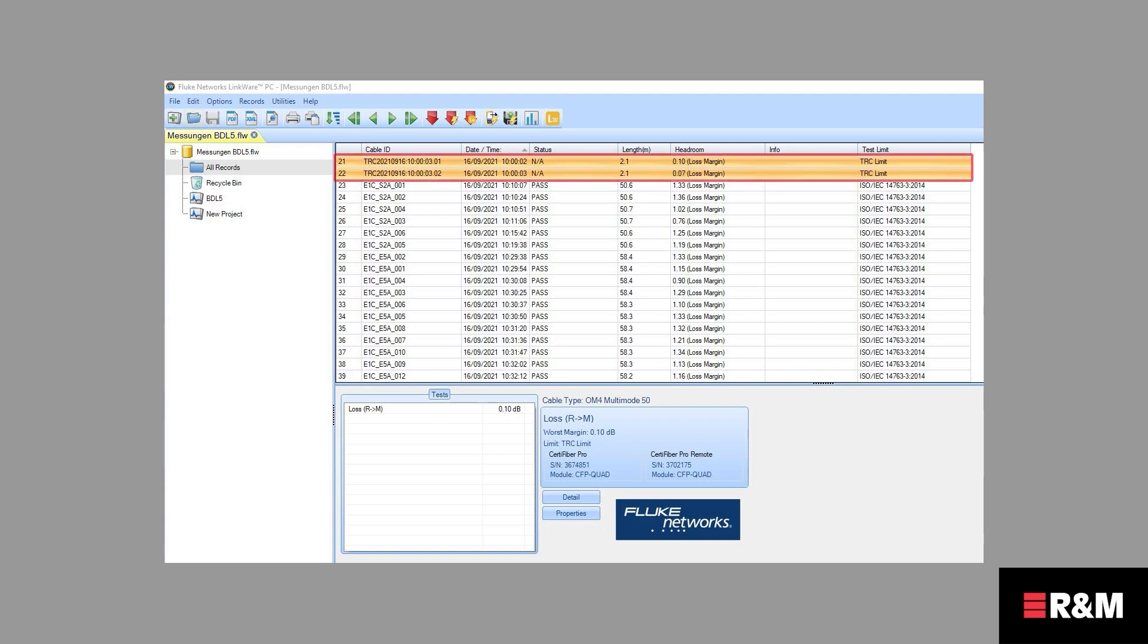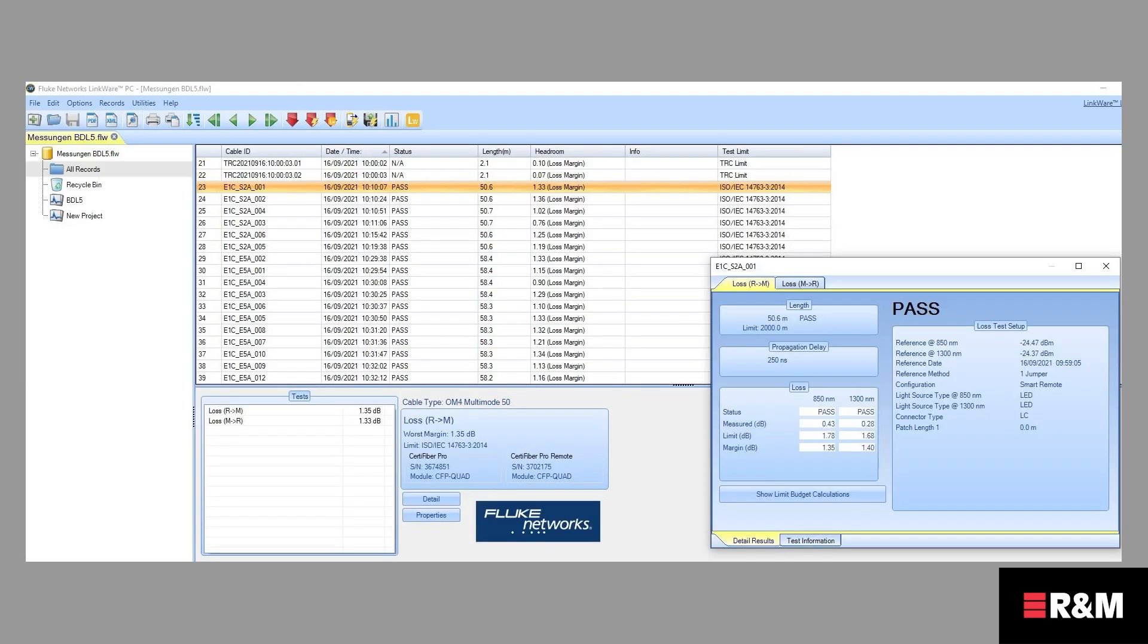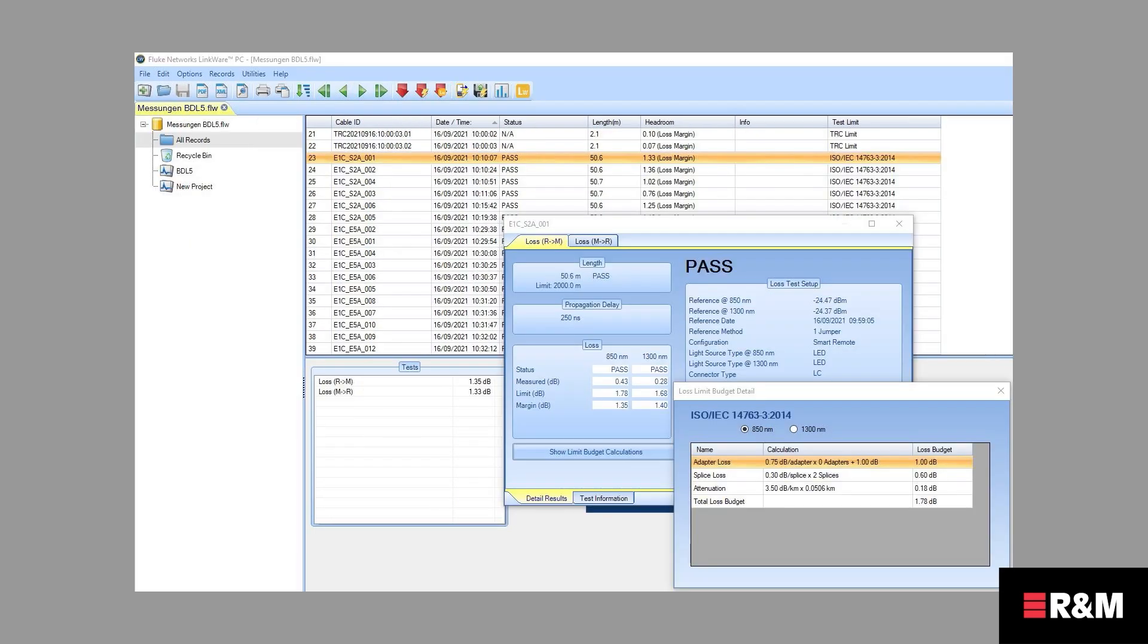You can see here the test reference cords as the top two results. This overview shows you the cable IDs, measuring data, status on pass-fail, fiber length, headroom, that is the loss margin, and the test limit standard and all the information that was selected as part of the referencing and verification. When you click on the Show Limit Budget Calculation button, you can see the calculation used for this link.